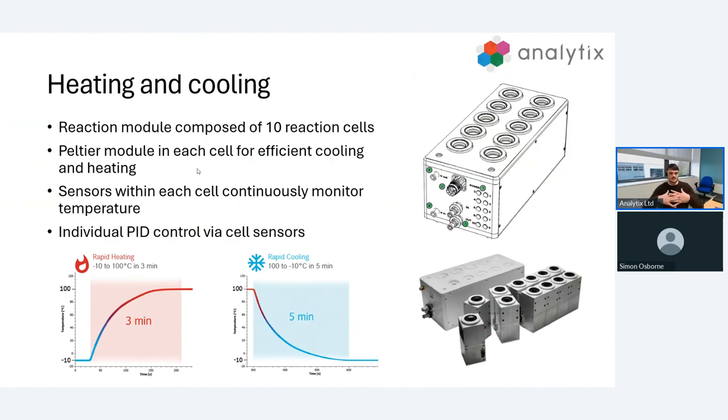Each of these reaction cells is made up of a Peltier module, which you can see in the bottom right of your screen. This Peltier module is capable of carrying out really efficient heating and cooling. Depending on the direction in which an electrical current travels through this module, we're able to heat or cool. We have sensors in each of the individual modules continuously monitoring the temperature of the heating jacket. The system is completely PID controlled, which enables us to get really excellent temperature stability.